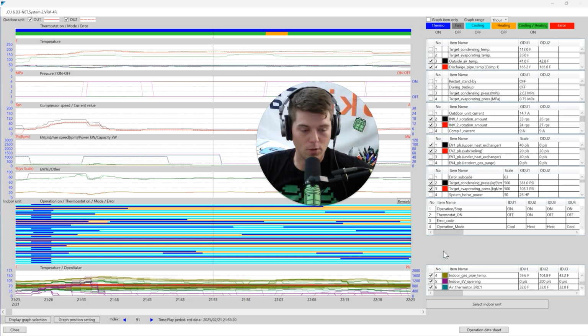But if you look here, the great thing about this is I can see both of my modules side by side, right? I can see that both my subcoolers are at 20 pulses. Okay, does this stay that way? Does it modulate that way?